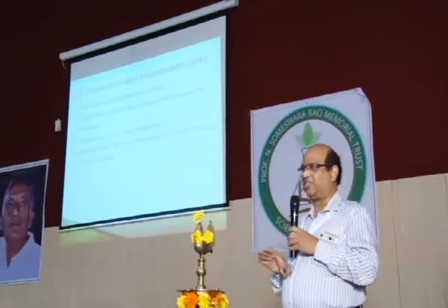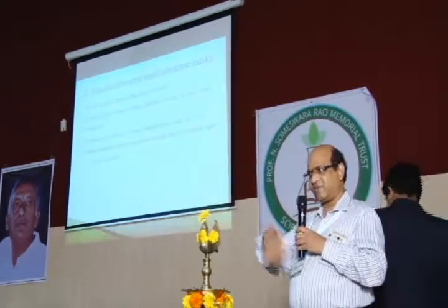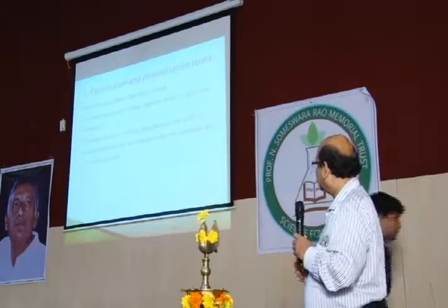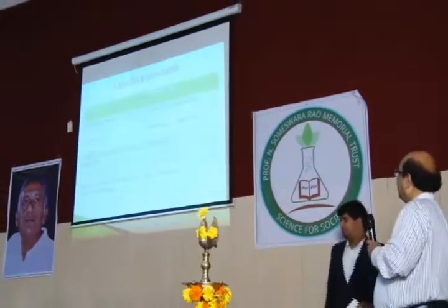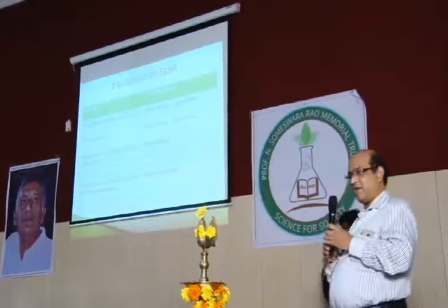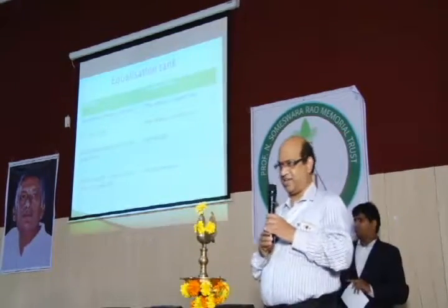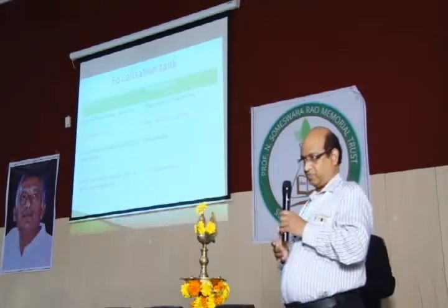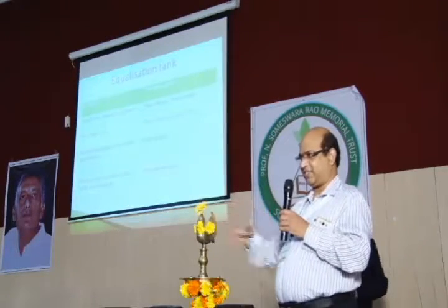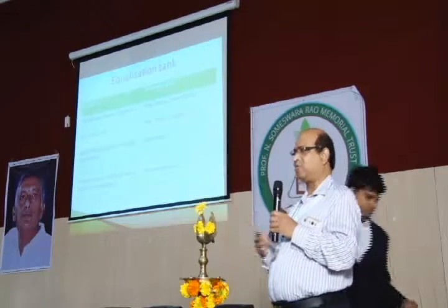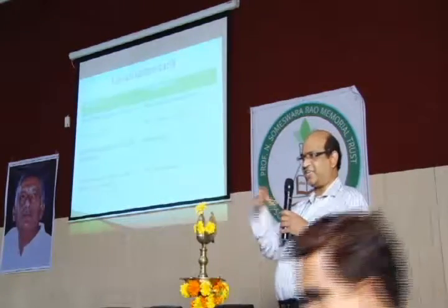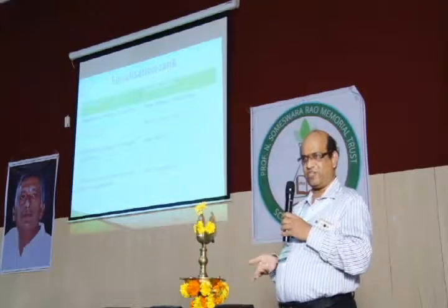So the equalization tank is very, very essential, and that tank should also have facilities like an agitator. Because sometimes what happens, the equalization tank after construction is insufficient. For example, 100 MLD capacity is there, but the tank capacity is very small. So sufficient mixing is not there, and because of stagnation, odor will come, because it is raw effluent.